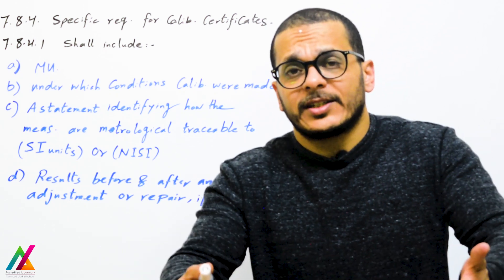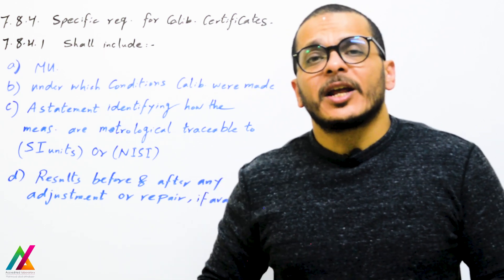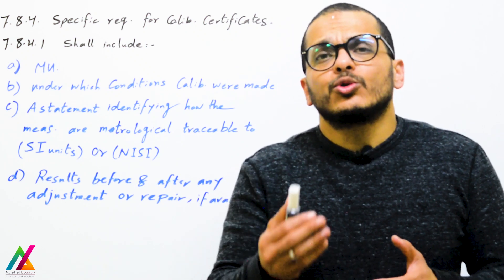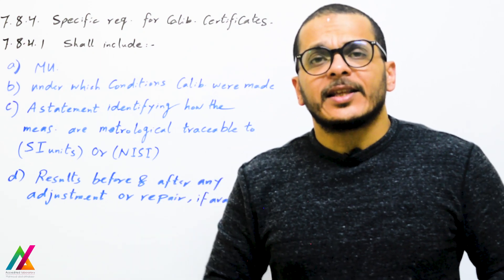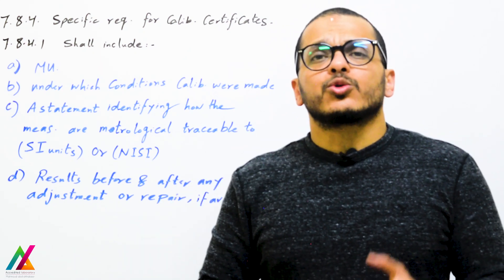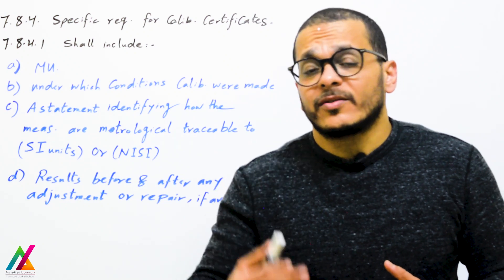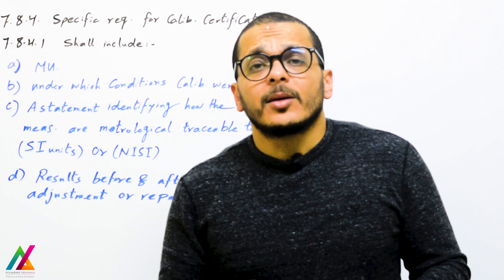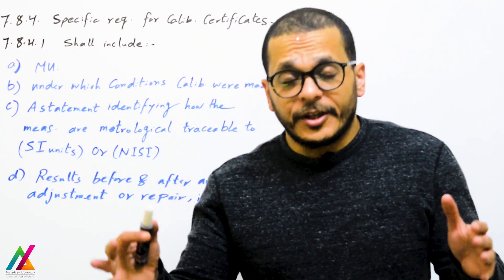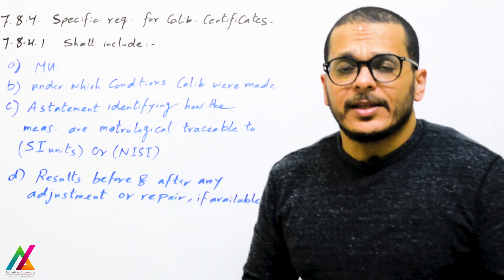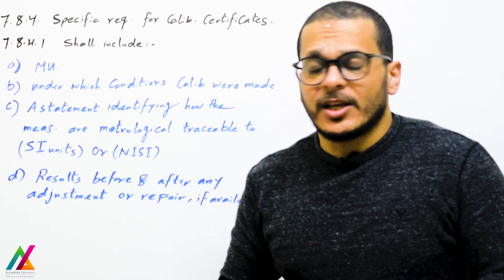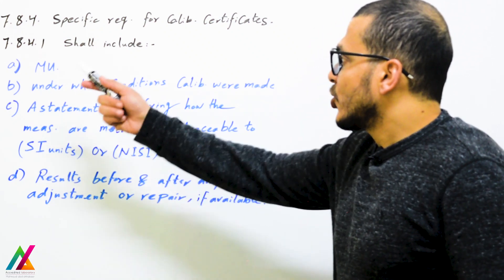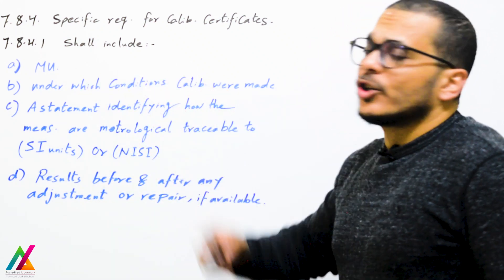Calibration certificates are only required for calibration laboratories, but other laboratories will request a calibration laboratory to calibrate their equipment. You should know what information should be in the calibration certificate, and also when you receive standards you will have a calibration certificate for those standards. So besides information from common requirements for all reports, you will need some specific information about calibration certificates.